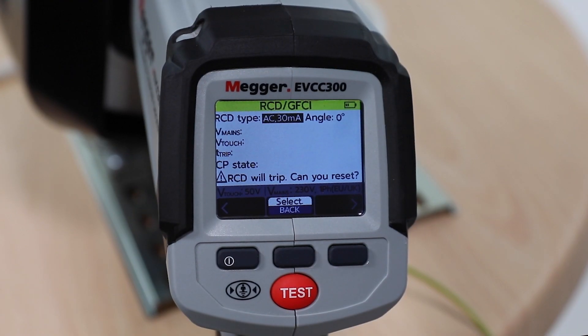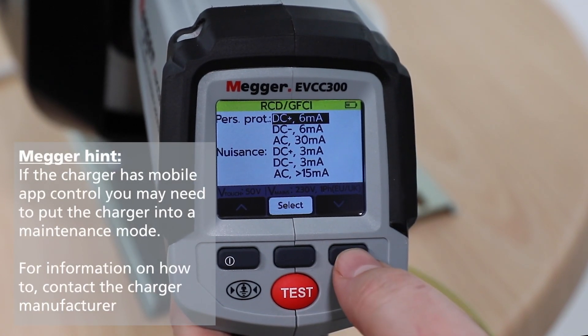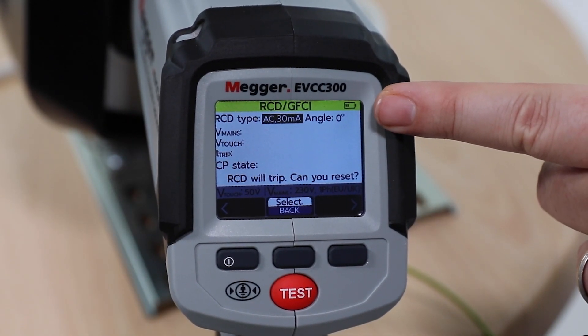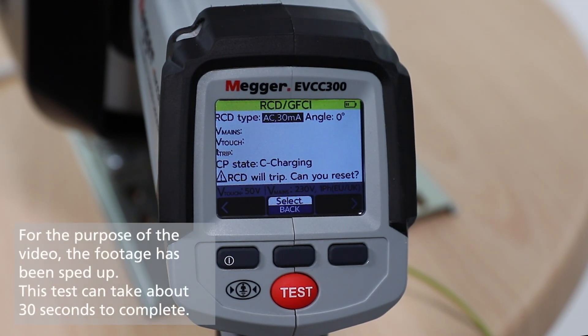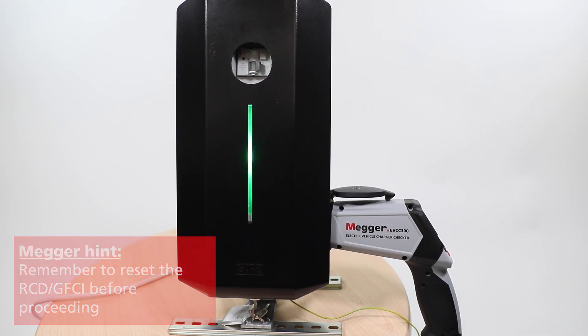Select the RCD/GFCI type that is used as a protective device on the EV charge point. Select the RCD/GFCI angle you wish to test first. Press the test button for 2 seconds and release. On-screen results will show mains voltage, touch voltage, and RCD/GFCI trip time. When the test is complete, remember to reset the RCD/GFCI.